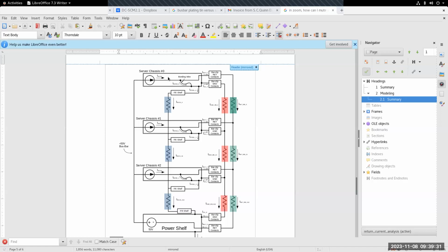The shelf was mated. The load was shut off, so there was no current being injected here. But 5 of that 20 amps went up through this path and then onto the return and down.